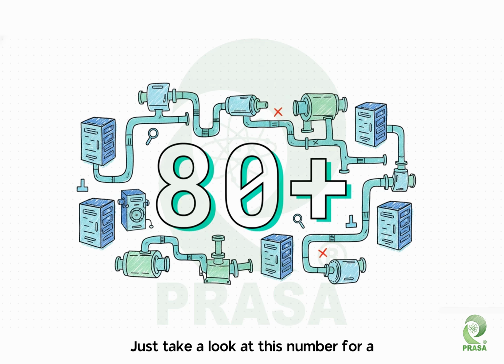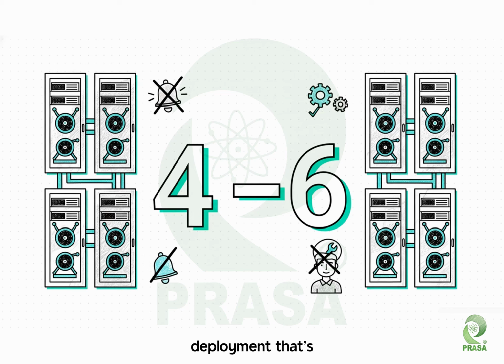Just take a look at this number. For a pretty modest 40-rack AI cluster that uses in-rack CDUs with dual pumps, your maintenance team is now on the hook for over 80 different pumps. Think about that. 80 potential points of failure, 80 things to monitor, 80 items on your maintenance schedule. It's an operational nightmare. Now, let's flip that and look at an in-row deployment that's cooling the exact same 40 racks. You're maybe looking at 4 to 6 pumps total. The difference in operational simplicity is just night and day.